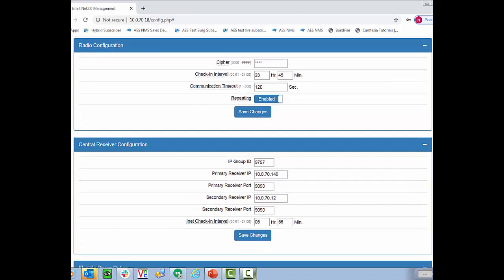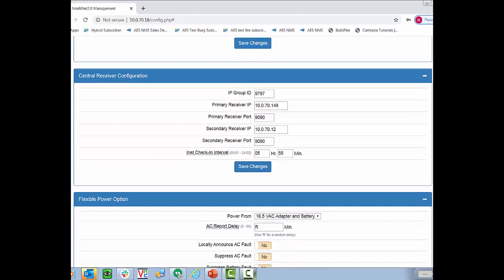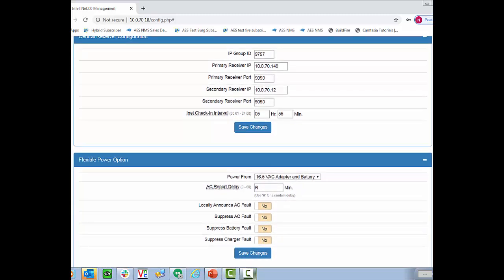Below that we have our central receiver configuration. This is if you're using the 2.0 radio to connect via IP. You need to enter the IP address primary receiver and the secondary receiver and then note that the internet check-in interval is going to be something less than six hours. We generally recommend five hours and 55 minutes.